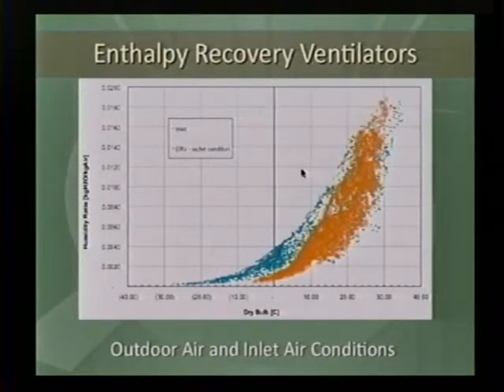The enthalpy recovery ventilator, if you looked simply at the energy content of the air coming into the building, was a little bit better than the earth tubes. What they did in the winter overcame what they didn't do in the summer. But you have a large friction loss in the fans to push through that heat exchanger for an enthalpy recovery ventilator. So you're adding a pressure drop to the fan system. We didn't have that in the 2-foot diameter sewer pipe that we used for the earth tubes. And so when you added the parasitic power in, the earth tubes work better.